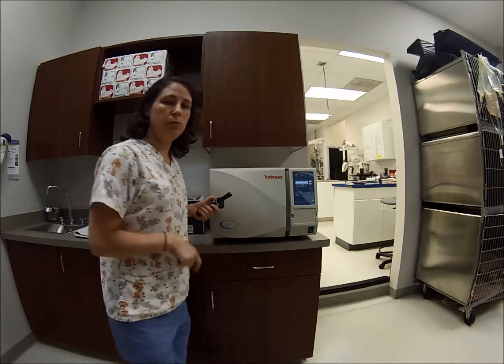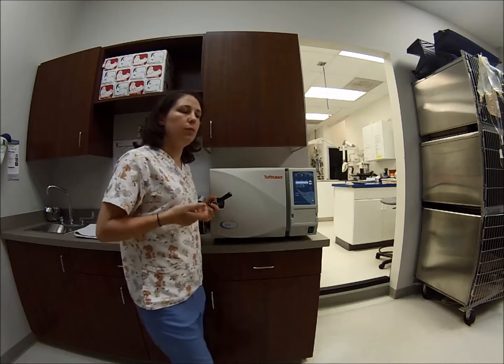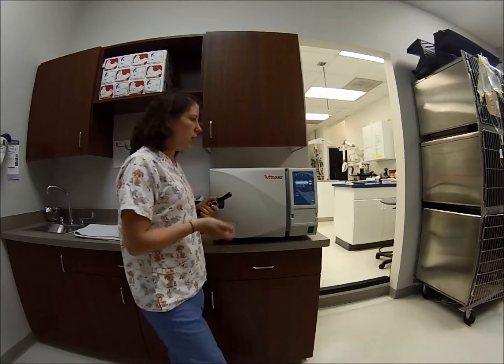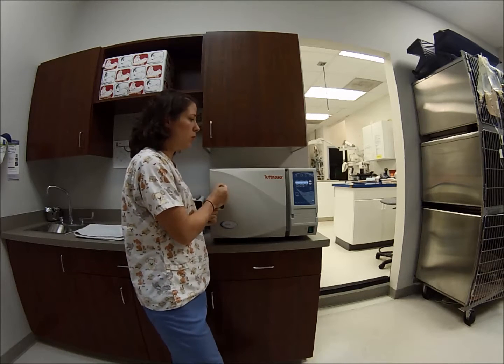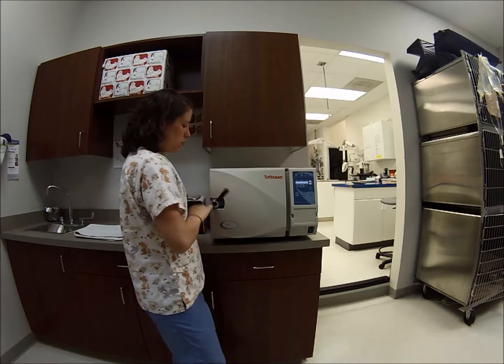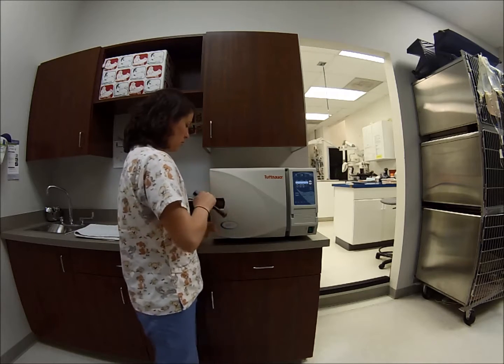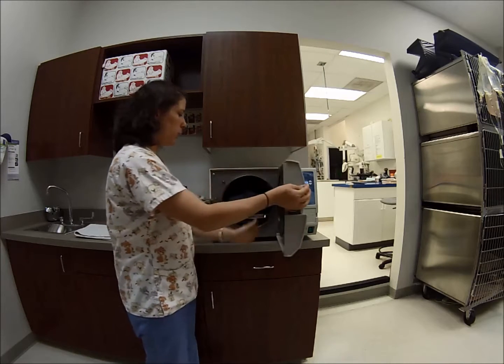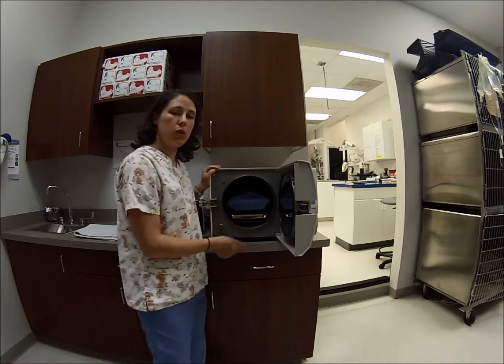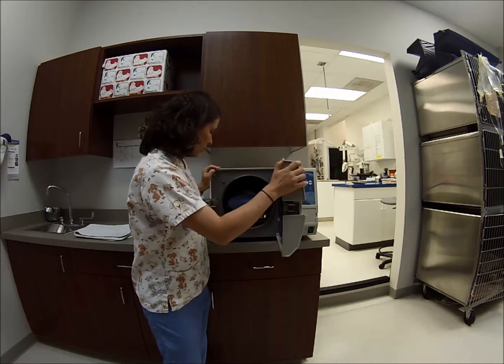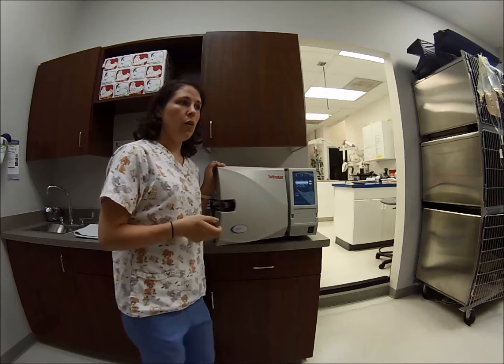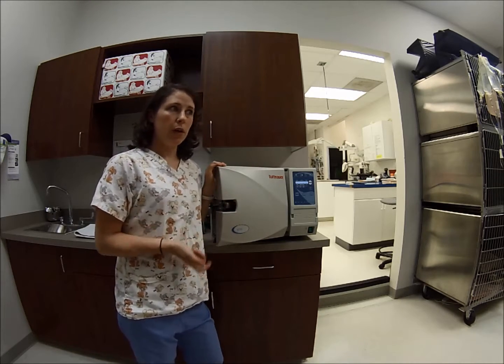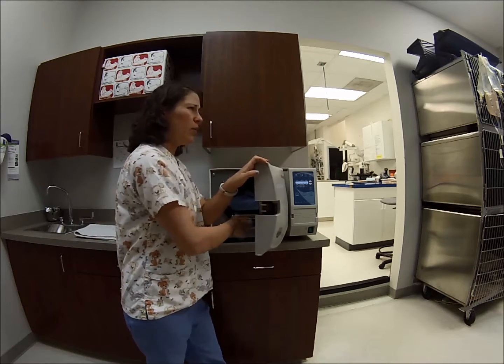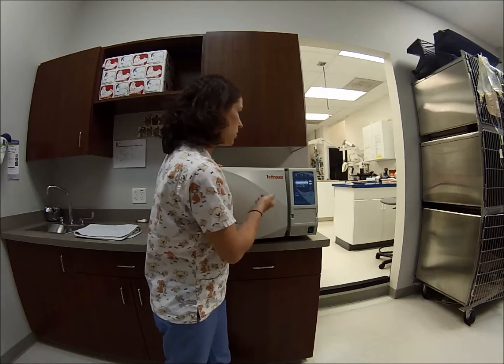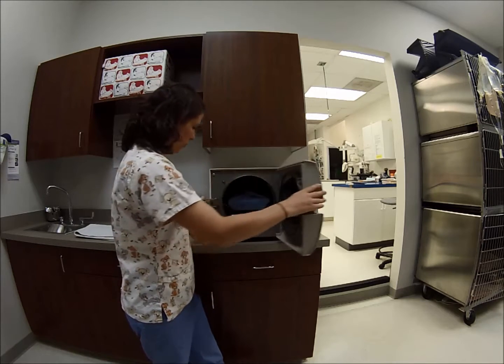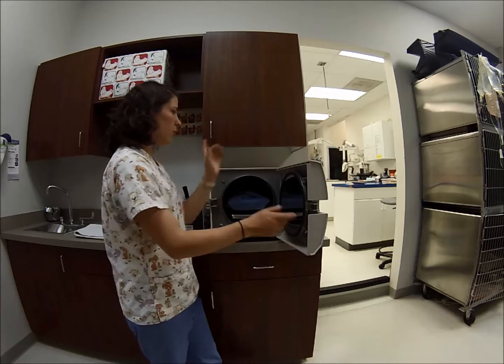Now, it's definitely important to do maintenance on your autoclave. We do weekly, monthly, and yearly maintenance. Once a week, it's a good idea to clean the autoclave, including the gasket door, which I'll just open back up here. With a mild detergent, we'll wipe the door, the interior of the chamber, we'll take the tray out and clean it. And probably about once a week, we will do a cleaning cycle. So we use a product called Chamber Bright, in which you pour in a powder product and you run a sterilization cycle without a drying cycle. And then when you're finished, you'll drain the water from this spout here and replace it with new distilled water.